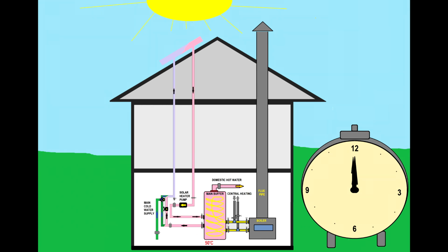But in the evening, when you are coming home, if you have children and you have to use a little bit more water, depending on the size of your tank, you will use the boiler. When you use the boiler, the ring circuit will be stopped, and the main water supply will go through the solar heater heat exchanger and come back onto this main buffer. So you will only transit the water through the solar heaters, and the water will reach the buffer a little bit warmer. And this is good, especially, guys, because for Legionella the tank should go over 60 as temperature to kill Legionella.